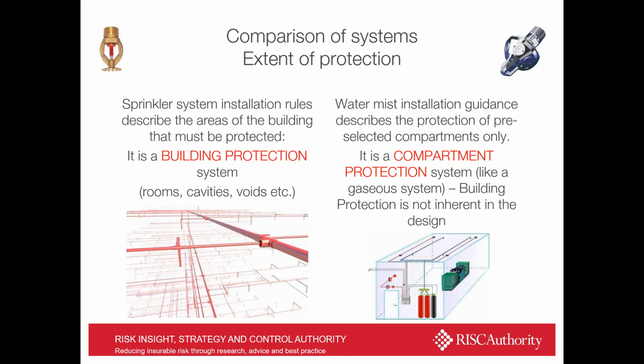When I'm confronted with people saying I don't know whether to put in a sprinkler system or water mist system, it's more than just talking about the technology and the methods with which it puts out fires. In specifying a sprinkler system, you are signing up to a list of rules that tells you every area of the building that has to be protected. And it's even the hidden areas, the voids, the cavities, if they contain combustible things. It is basically a total building protection system that is being signed up to, not just the fact that you're using a nozzle that puts out big drops.